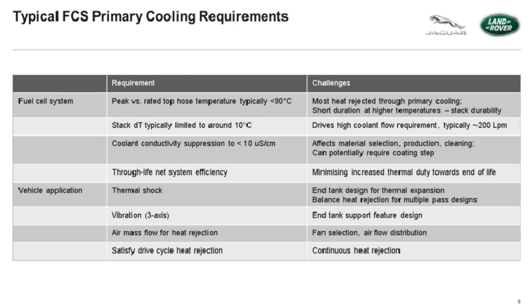The coolant conductivity itself has to be suppressed to about 10 microsiemens or lower, and this affects things like material selection - we have to be careful about what kind of materials and metals we use, but also plastic parts and hose materials. From a production point of view, this brings certain requirements, and for certain applications a coating requirement might be introduced. From a thermal shock point of view, we have to ensure end tanks have been designed for thermal expansion, and we have to balance the duty on the front and rear pass.